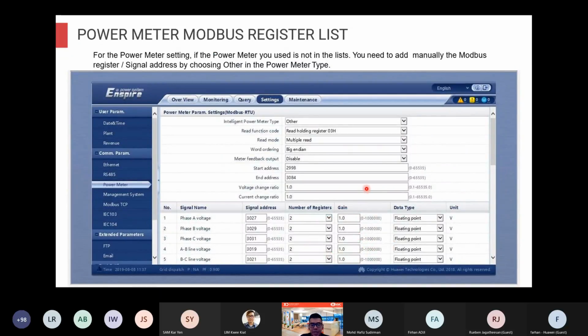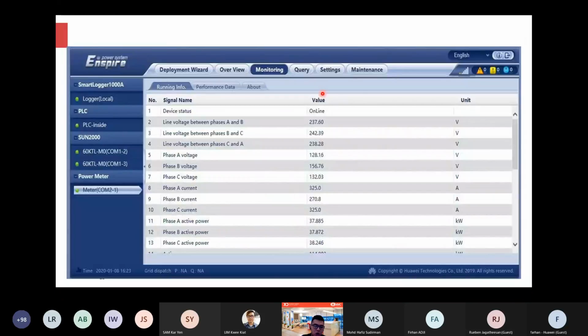What this gain basically means is the decimal point. So if you want to times 10 or divide by 10, that's referring to the gain. You have to check your monitoring system whether the number makes sense, because it doesn't make sense to have a line voltage of 2370. So always check - does this make sense? If not, change the decimal point at the gain part.